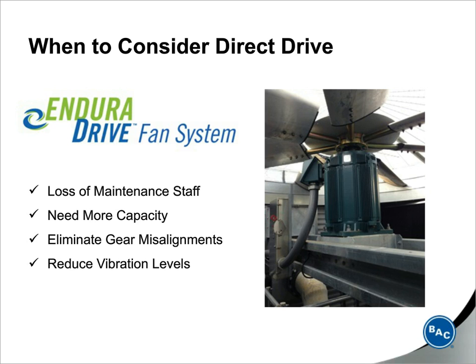Now, in addition to selecting a unit with a direct drive system, if you're going to replace an existing gear system, this could really be the perfect opportunity to replace it with a direct drive system. And then also, if you've had excessive vibration from wear and tear on the existing drive system, a direct drive system can be really an excellent solution for vibration reduction.